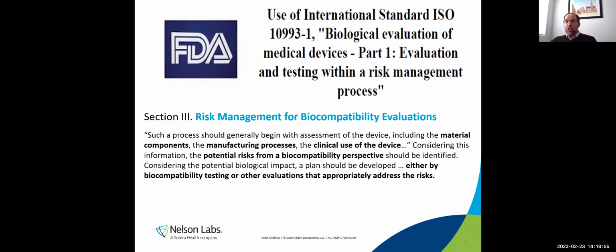We look at, are we changing materials? Are we changing processes that can directly or indirectly contact the patient? How's the device used? Based on those three inputs, we make a conclusion about either, do we feel like testing is needed to help us feel good about these changes, or do we feel good that we've mitigated any risks, or do we have risks that we need to mitigate, and can we justify it?